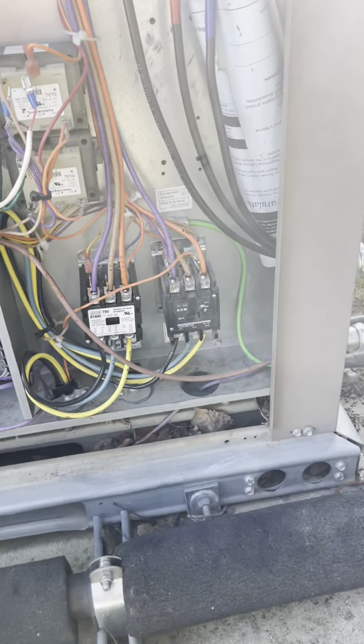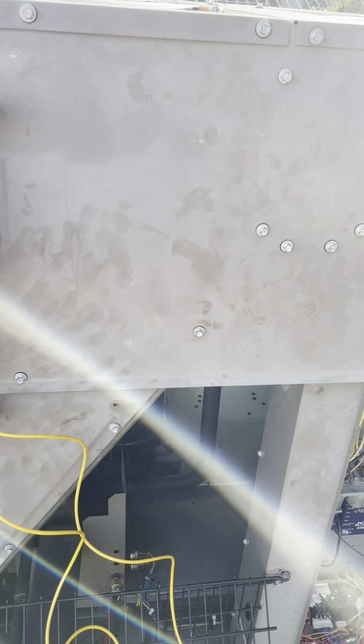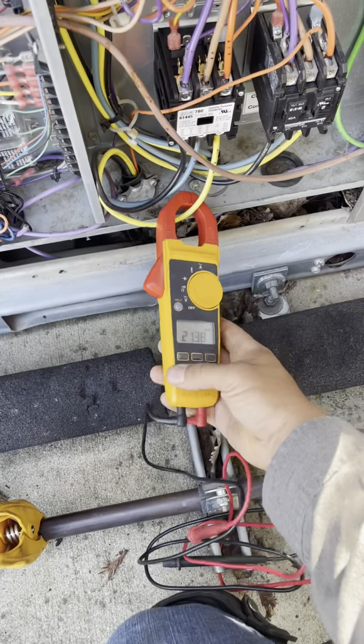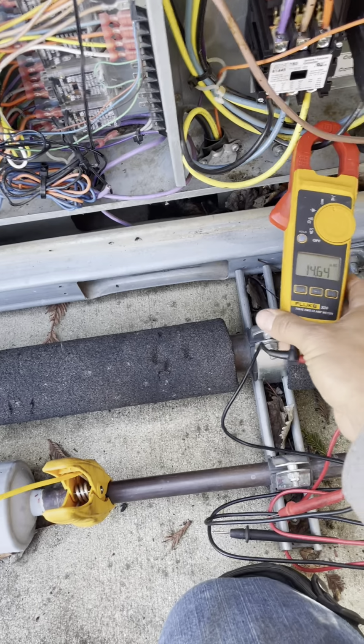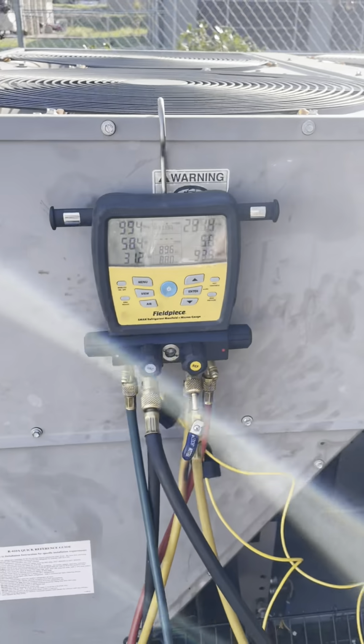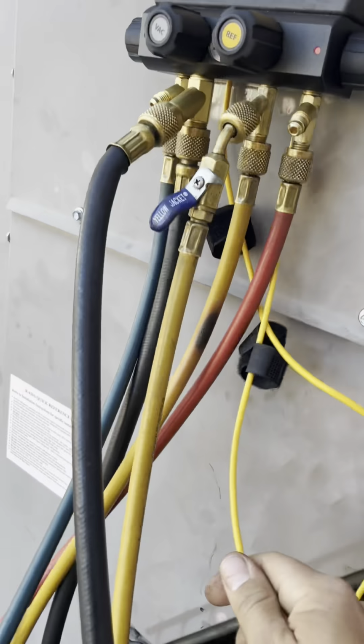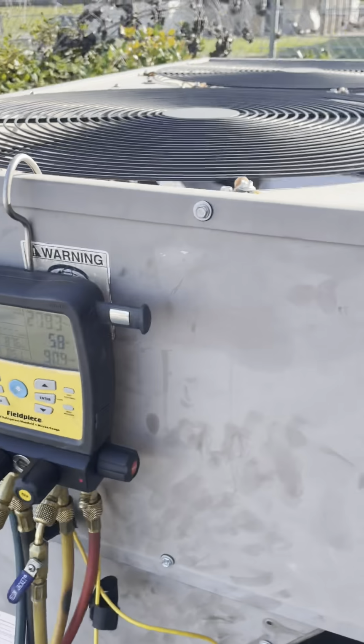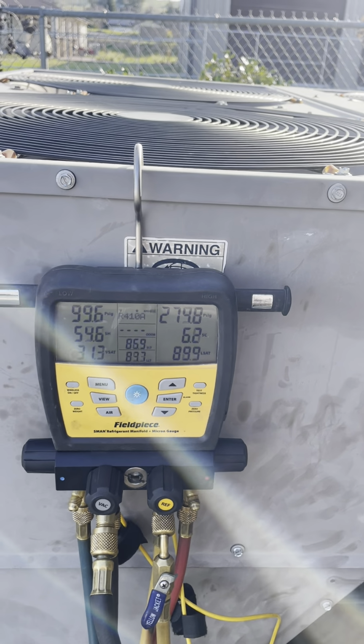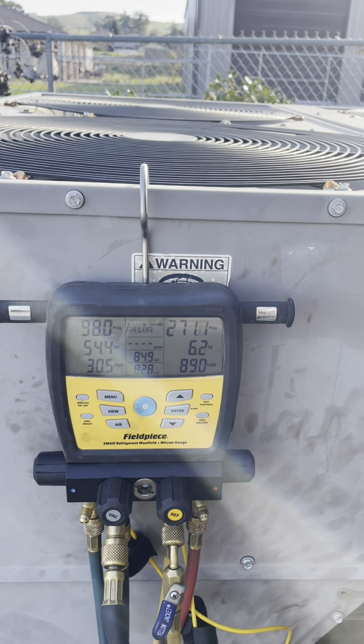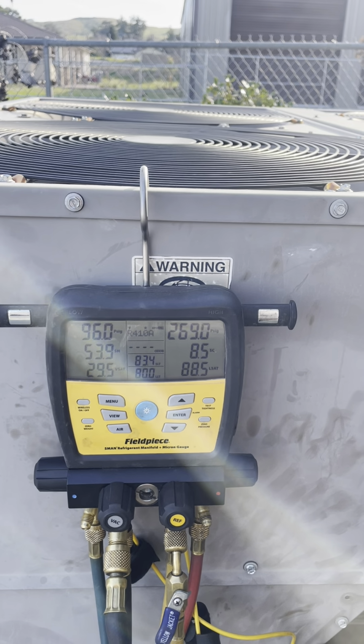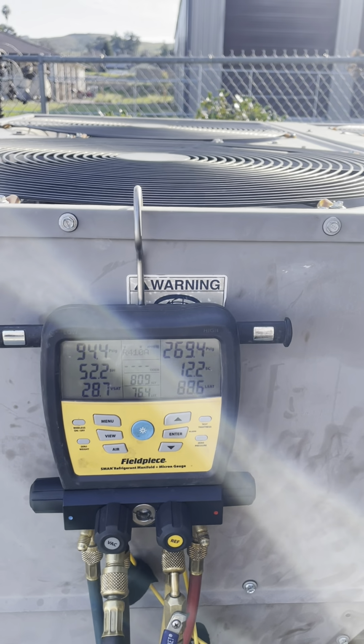Okay, so we got both compressors running now. And that supply plenum felt really cold, so I'm pretty dang sure our superheat's gonna be low now. Let's make sure both compressors are running. Yeah, both of them are running. My liquid line's warmer now. Oh, really? Oh, okay. That's funny. My filter dryer, it might be a little bit restricted by maybe 2 degrees. It kind of looks like it is restricted a little bit.